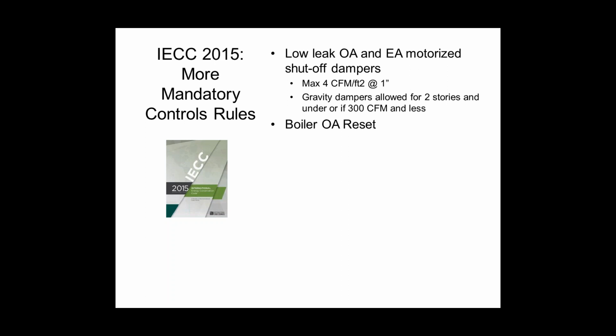Boiler outside air reset is mandatory. You have to do it. It's not optional. You cannot run your boiler at 180 degrees all year long. You need to reset it based on something. We'll talk about that in a little bit, but typically you're going to reset it based on outside air. The cooler it is outside, the warmer the water I want, and then the warmer it gets outside, the cooler the water I can use.